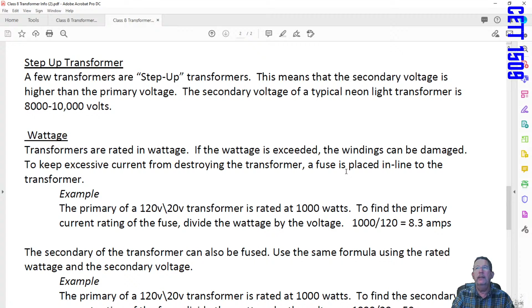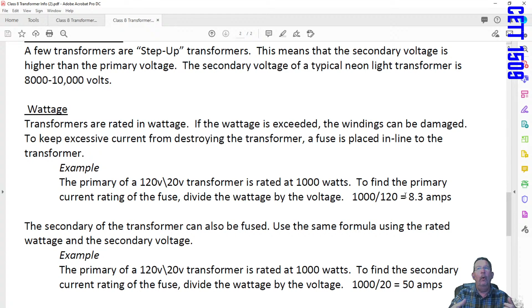The primary of a 120 volt, 20 volt transformer is rated at 1,000 watts. To find the primary current rating of the fuse, you divide the wattage by the voltage: 1,000 watts divided by the voltage gives 8.3 amps. So I'm going to fuse it maybe for 8 amps, maybe for 5 amps, just depending on the application.